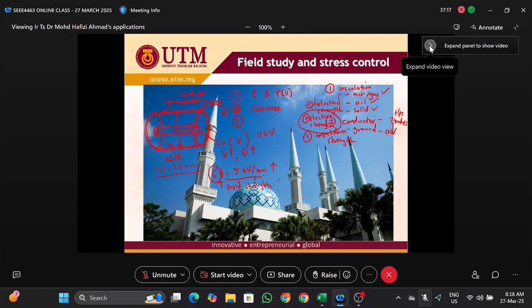Okay, we are going to see how we derive the equations. All right, for electrical engineers, we understand that the electric field, called field strength, should be less than electric strength. This is in order to prevent any failure or premature failure, something like partial discharge, right, to prevent any sparking or arcing that may happen due to non-uniform electric fields.